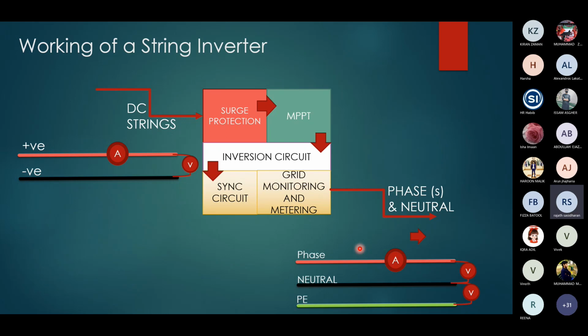What you will see inside it is there will be some terminals for the DC cables to be plugged in, and it will have a surge protection. Then there will be a circuit for the maximum power point tracking, and there will be an inversion circuit with IGBTs, of course. Then there will be a synchronization circuit because you are pumping this converted energy into a grid, right? So the grid will be 240 over 415, or depending on different countries, the voltage will be different, the frequency will be different. So there is a sync circuit required, and there is continuous monitoring and metering.